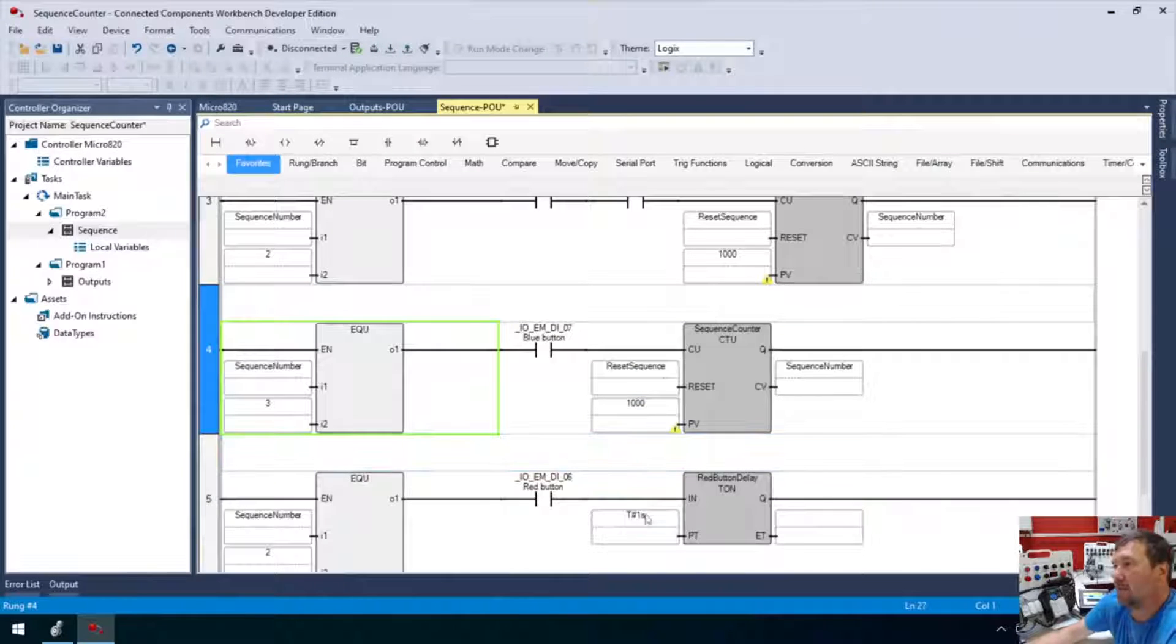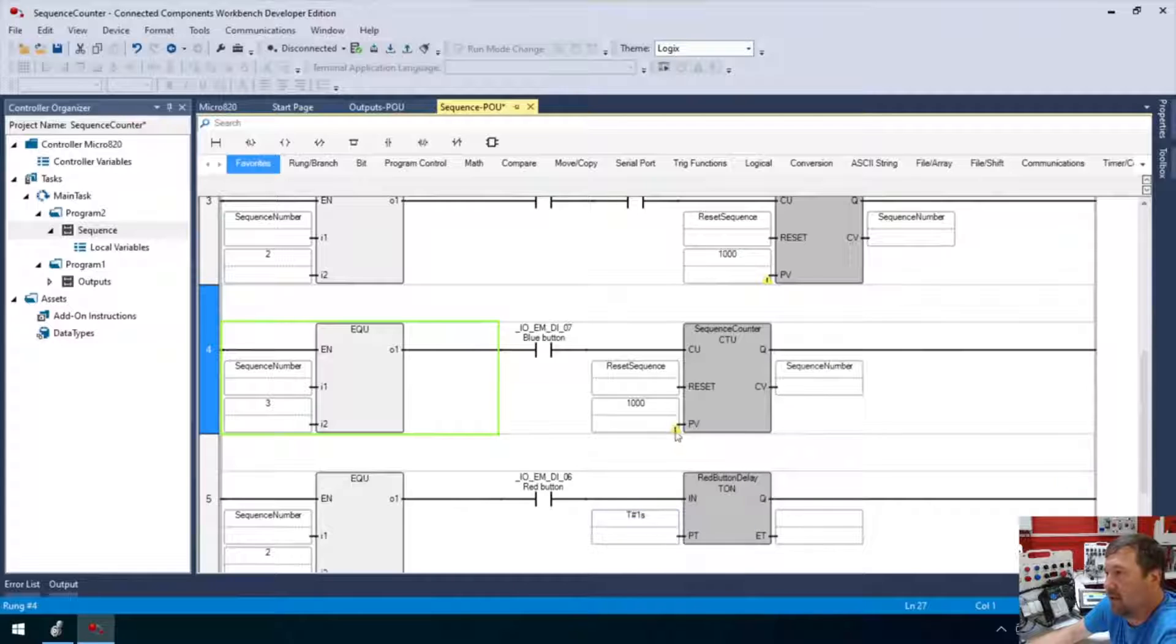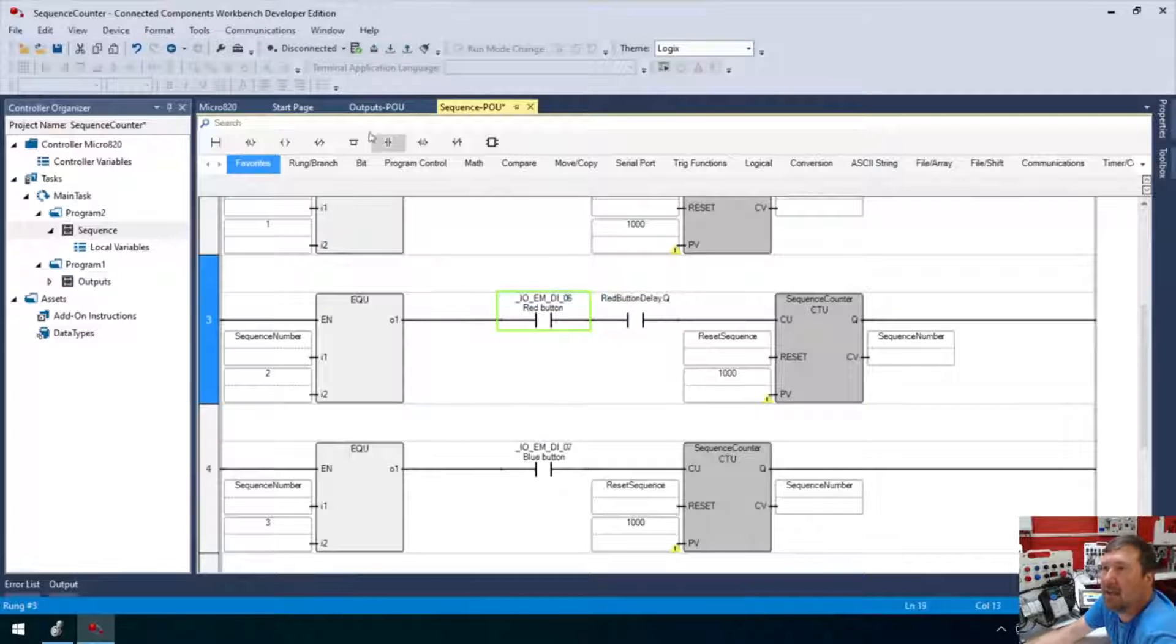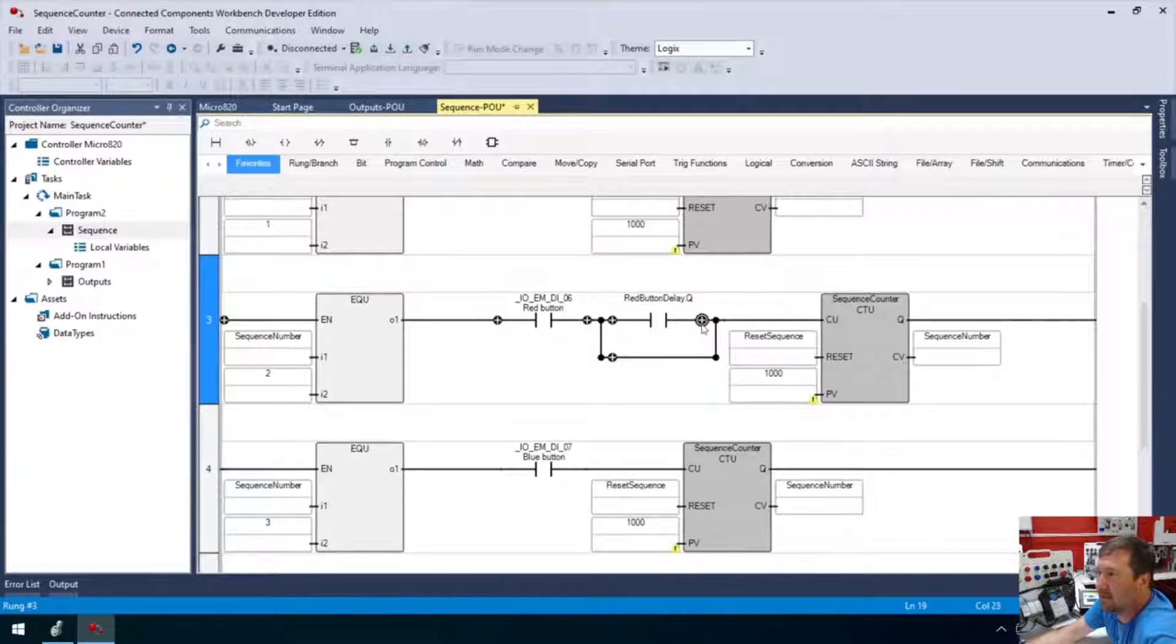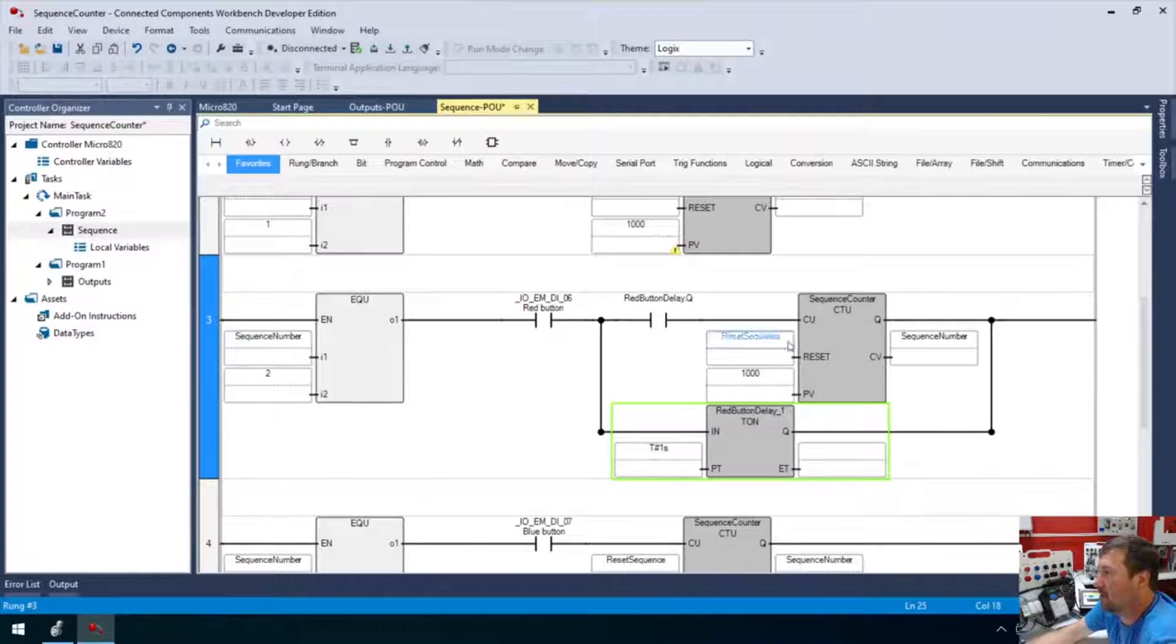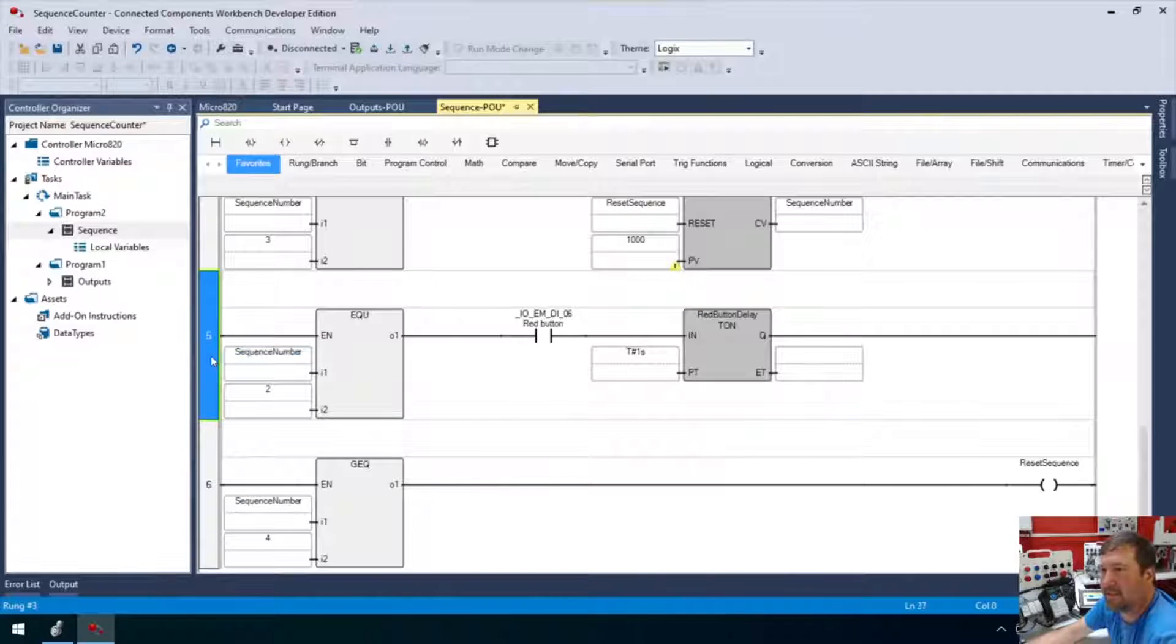Now we have this TON, which I didn't like stranded down here anyway. So I'm going to copy it now. I'll just right click, make sure I right click that way. I can make sure y'all see exactly what I do. Now we go up here to sequence number two. And here's where we're looking at that. I'm going to put a branch in here. I'm going to drag this in and I'm going to drag this in. And I'm going to put that TON right here. And I just think that's going to make it read so much better and make it where we can, I think it will make our troubleshooting a lot better. So now we can delete this.